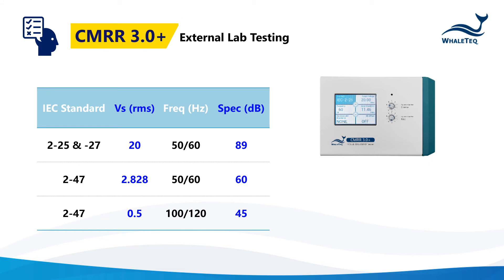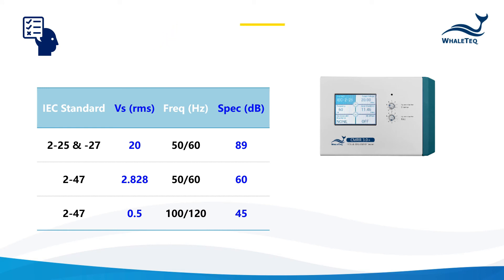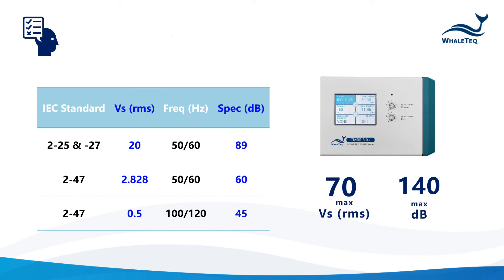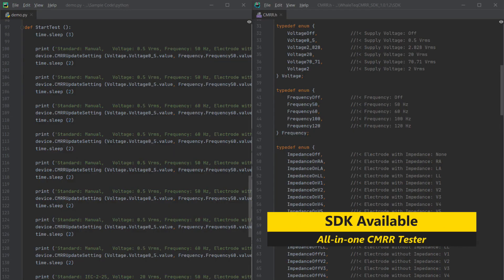WhaleTeq's CMRR solutions are standard compliant and popular among certification laboratories, so you can use the CMRR 3.0 Plus with confidence. But our goal doesn't stop at helping you meet standards — we want to help you create the best possible medical device, not only meeting but exceeding existing CMRR standards. That's why CMRR 3.0 Plus provides a maximum of 70 volts RMS, demonstrating balanced CMRR of up to 140 decibels. We also have an SDK available for you to run customized test sequences to demonstrate your product best.